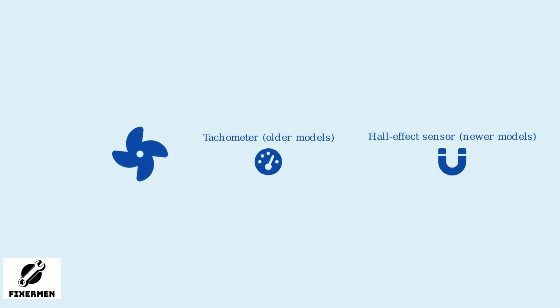The indoor fan motor uses a tachometer in older models or a Hall effect sensor in newer ones to report its rotational speed to the control board. This feedback loop is crucial for proper operation. The tachometer or Hall effect sensor detects the motor's speed and sends a signal back to the control board, creating a feedback loop that monitors performance. If the signal is missing or erratic, such as when motor speed drops below a certain threshold like 100 RPM, the system triggers the H6 error as a safety measure. This prevents motor burnout or further damage by halting operation when the system cannot confirm the fan is running properly.